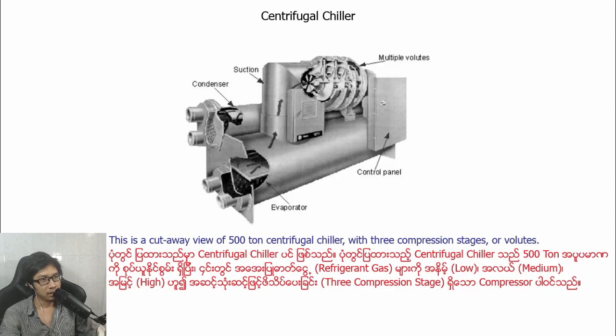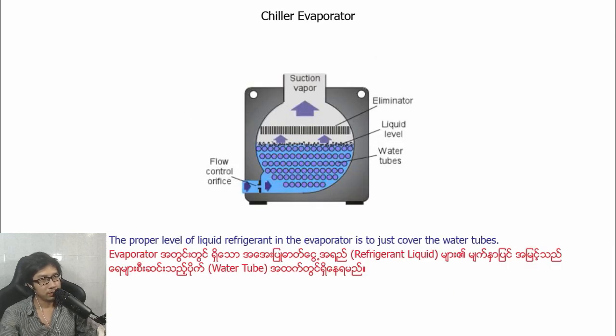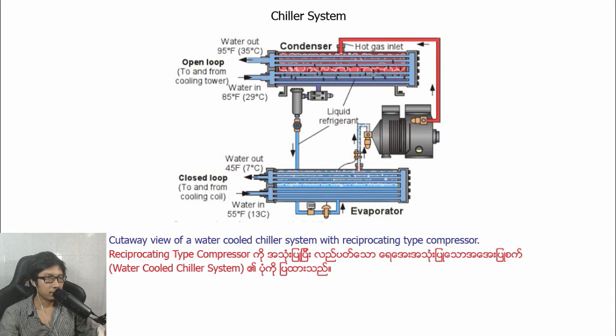Centrifugal chiller. This is a cutaway view of a centrifugal chiller with 3 compression stages, or volutes. Chiller evaporator. The proper level of liquid refrigerant in the evaporator is to just cover the water tubes. Chiller system. A cutaway view of a water-cooled chiller system with a reciprocating type compressor is shown in the figure.